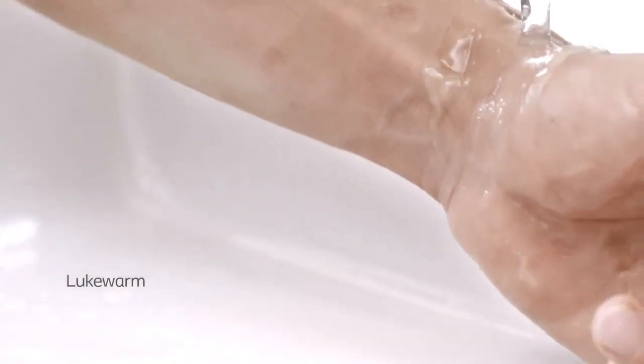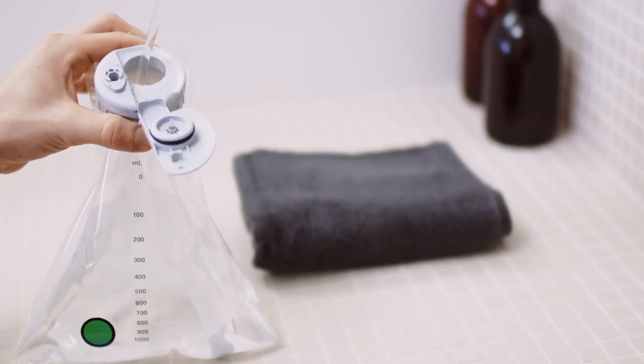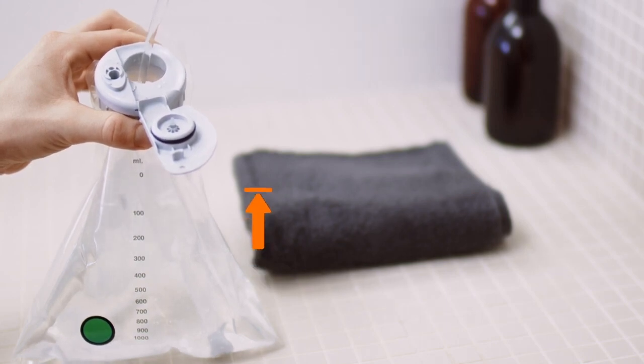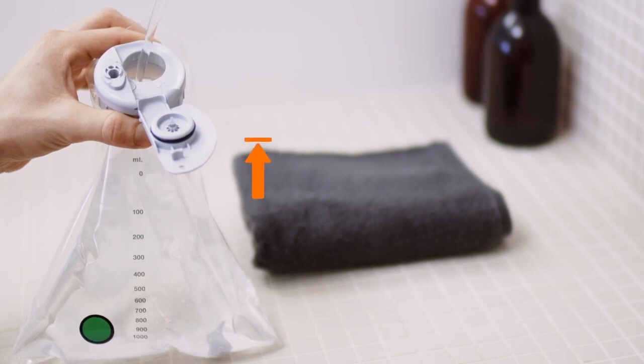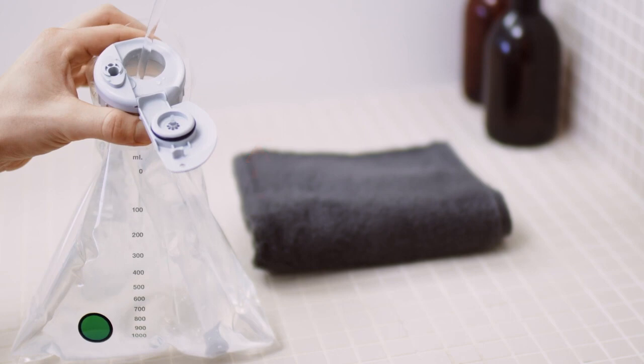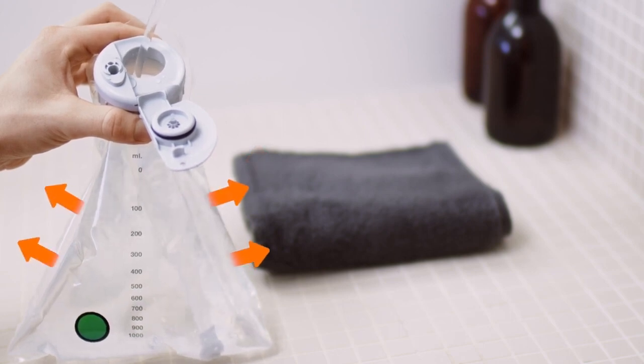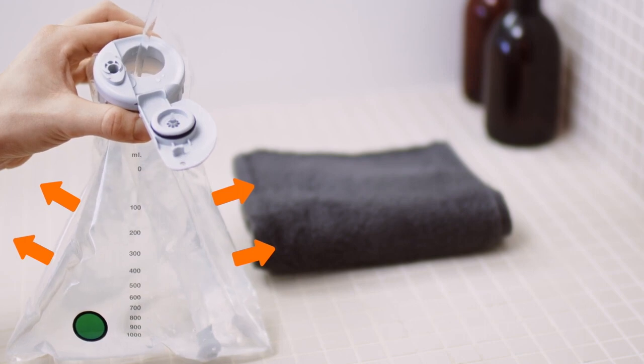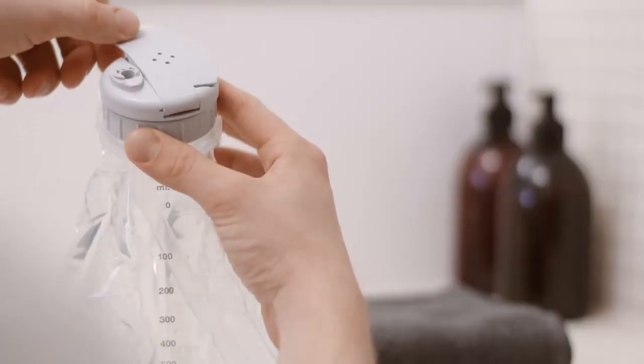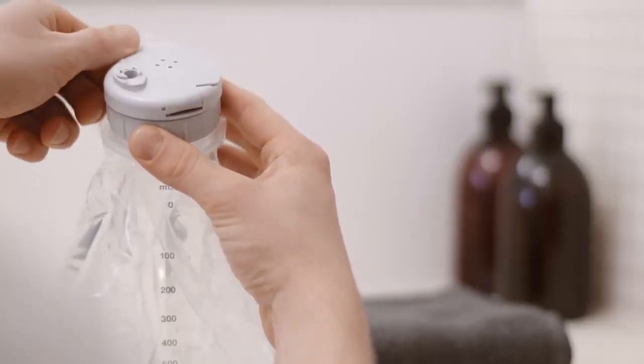To properly read the volume scale on the bag, you will need to fill the bag completely, all the way to the gray lid, even though you may not use all the water for the irrigation. The 3 water bag compartments fill up gradually, one after the other. Give the water bag time to expand and make sure all 3 compartments are completely filled with water, up to the lid. When you close the lid, make sure you hear a click, otherwise the system will not work properly.